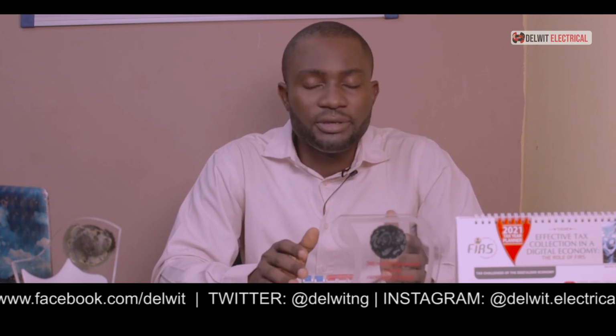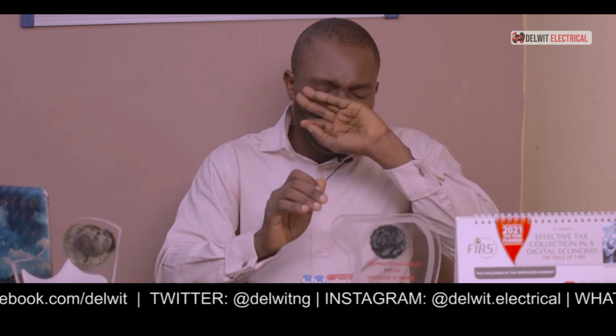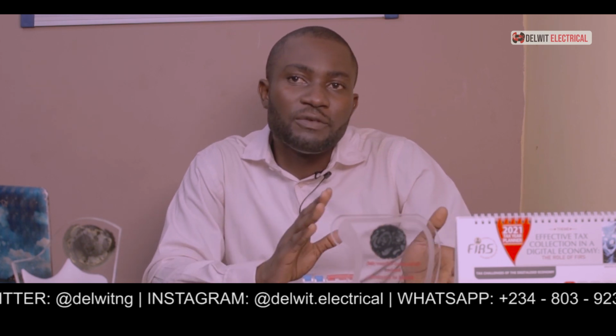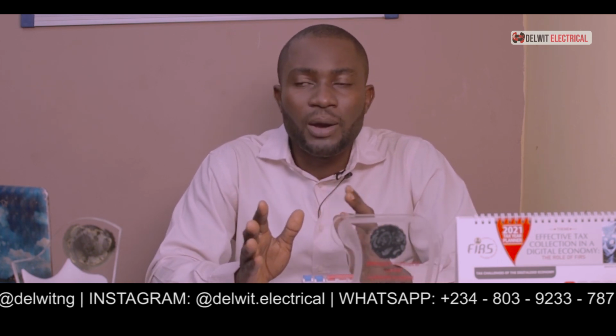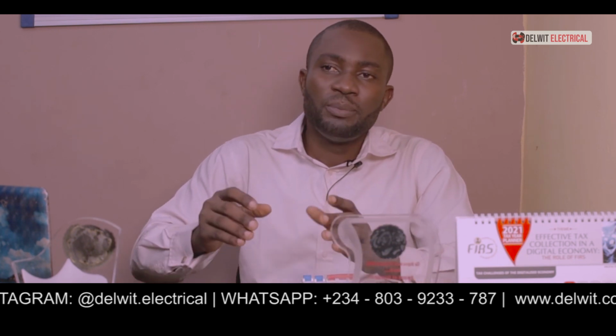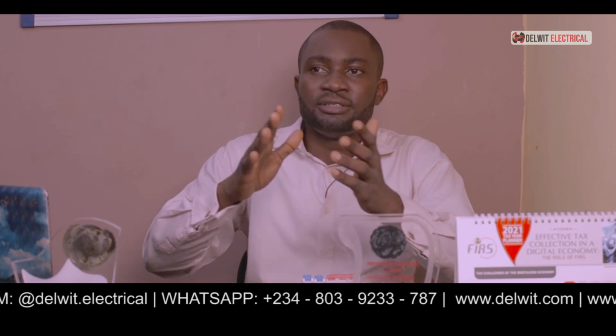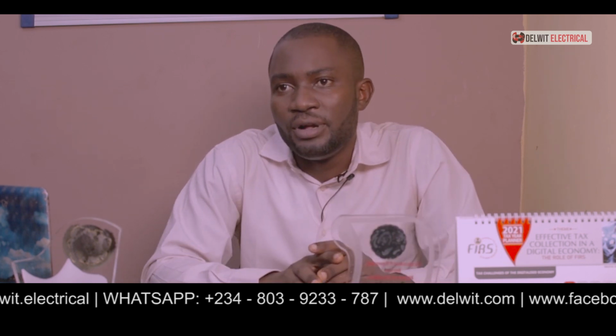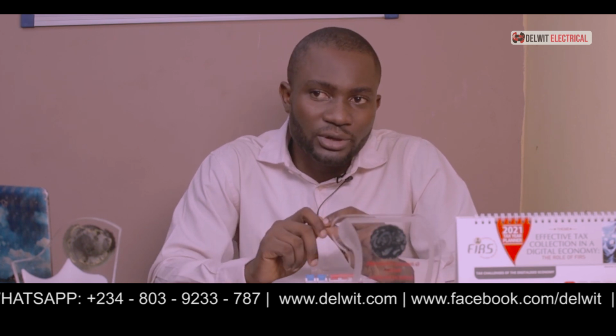The second aspect is short circuit. Now, this is very, very risky. With your circuit breaker, if it's not an overload, it's usually a short circuit. And what is this short circuit? A short circuit is when there is a touch between the live and the neutral of a building. So if you have a live wire and a neutral touching each other, it will continue to trip that particular circuit. So when a circuit is tripping continuously, you start doing fault tracing.